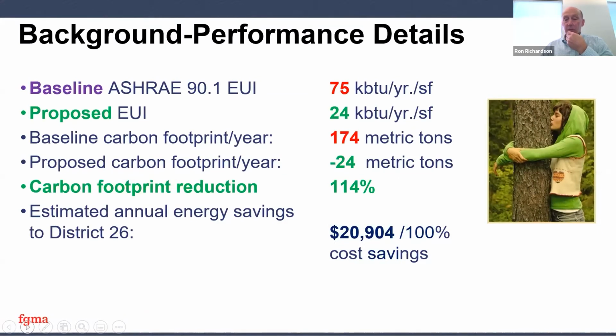Now for building performance — I'll give you specifics on how the building performed, because it was really a dramatic transformation from before to after. The baseline EUI for this facility was 75, under the baseline hot water HVAC system. The proposed EUI is 24, and the building just came online in August.